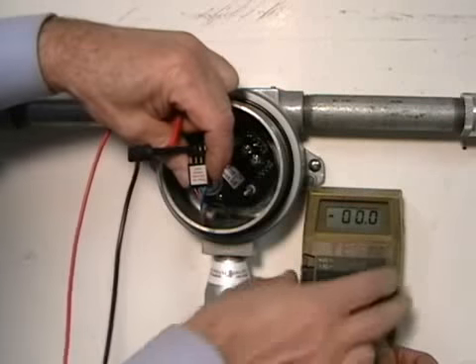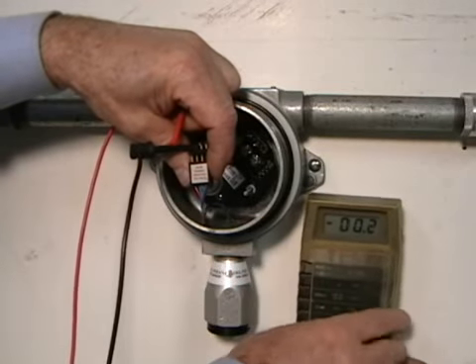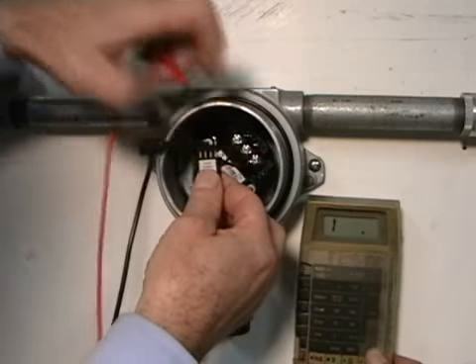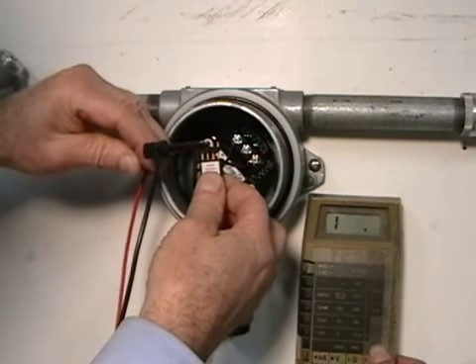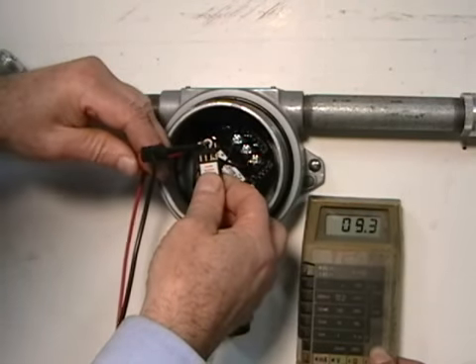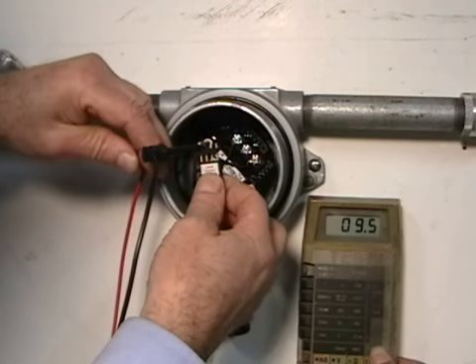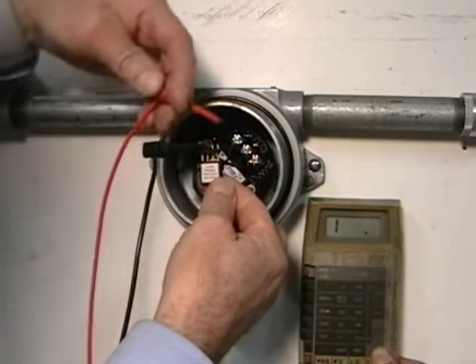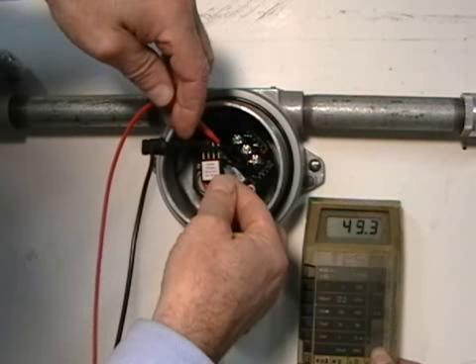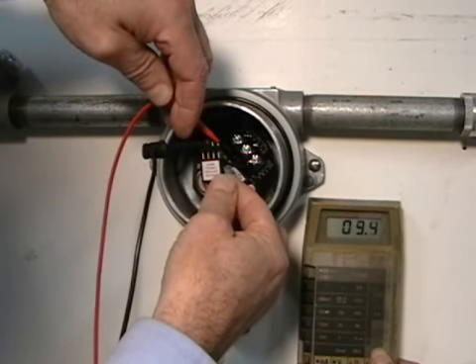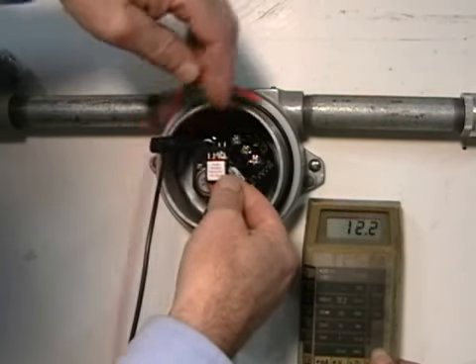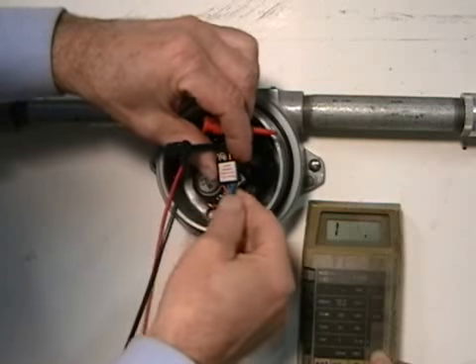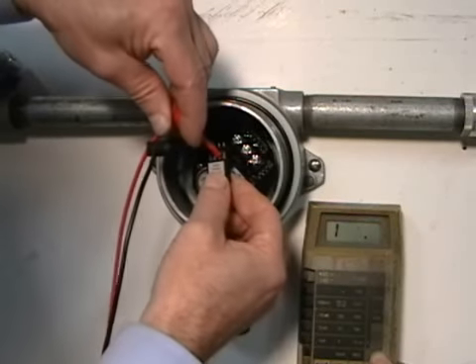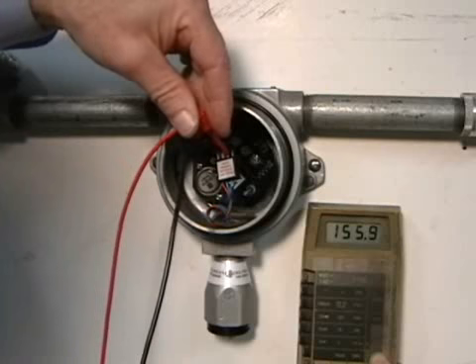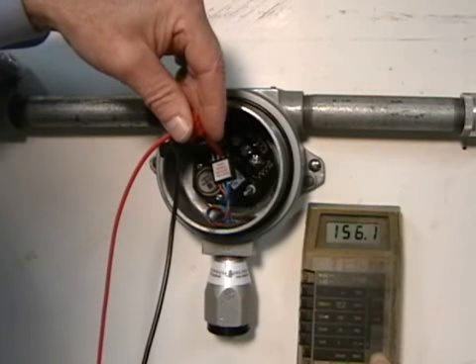To perform this test, set your DVM to ohms and using the test probes, check between the green and red wires of the sensor for the condition of the active bead, then the green to black wires for the condition of the reference bead. These values are typically between 8 to 12 ohms. The final check is between the green and blue wires for the condition of the coating resistor potentiometer. This value needs to be between 154 and 190 ohms.